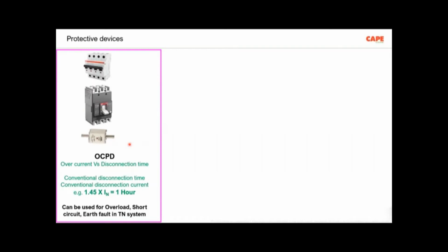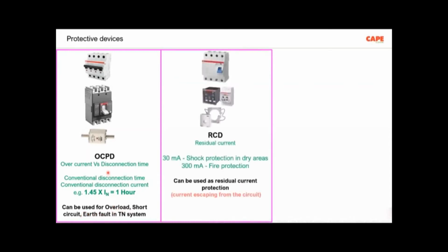The overcurrent can be caused by overload, short circuit, or earth fault in a TN system. So OCPDs can be used against overload, short circuit, and earth fault in a TN system. Of course, overload and short circuit in all the systems, and earth fault in TN system. Then the second protective device is called RCD, residual current device. We call it RCCB, or CBCT plus the earth fault relay.